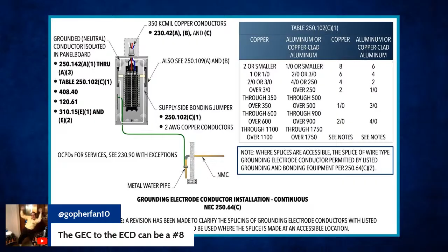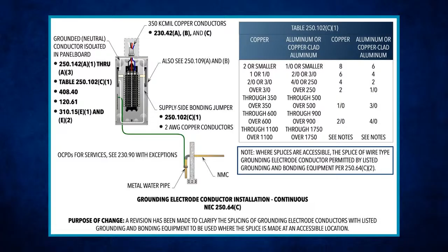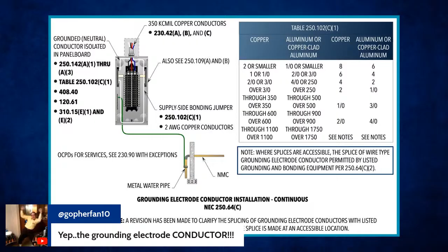I 100% agree. I mean, it's out of control. I mean, when these guys do this, dude, the GEC to the ECD can be a number 8. Oh, man. See, listen, okay, there you go. Then he says, yep, the grounding electrode conductor. No, you wouldn't have made that statement up above. You just proved you don't know what you're talking about. This honestly is embarrassing. It is. It is a number 4 concrete encased electrode grounding electrode conductor.